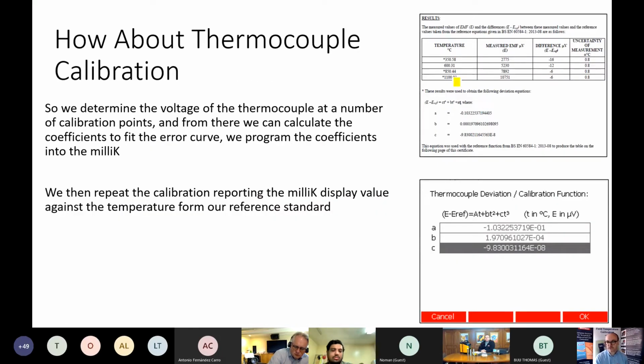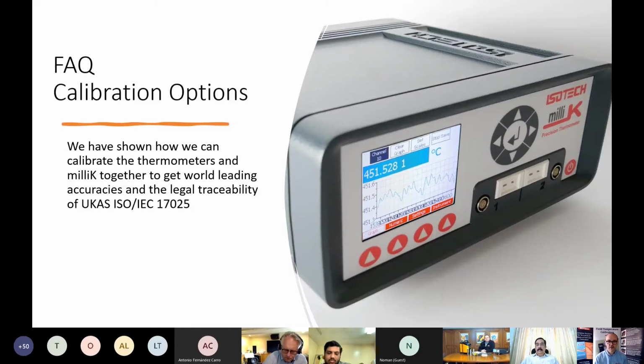So what happens is on the calibration certificates, we'll have the measured temperature and then the measured EMF. Then we'll look at the error, the difference between the two. And then we've got this equation here, which fits the error curve. So we determine the voltage of the thermocouple to the number of calibration points. And from there, we can calculate the coefficients to fit the error curve. And like with the PRTs, we program those coefficients into the milliK. So this is the milliK screen where we've taken the coefficients on the certificate and put it into the milliK. And then again, same as with the PRTs, we repeat that calibration and report the milliK display value against the temperature on the calibration certificate.